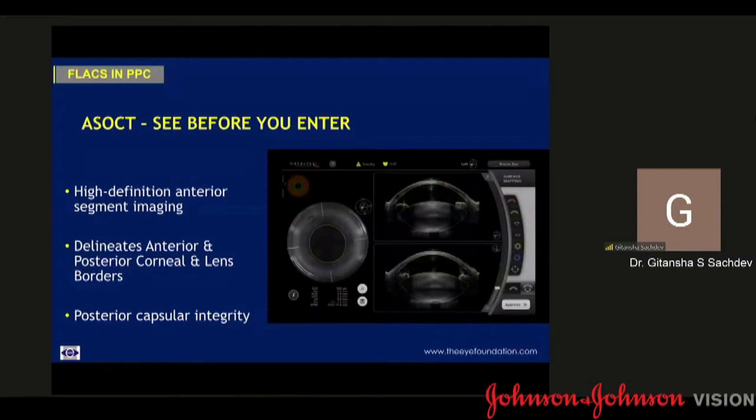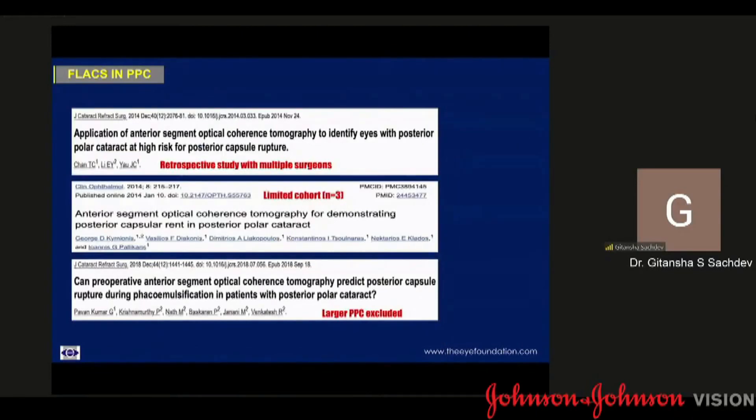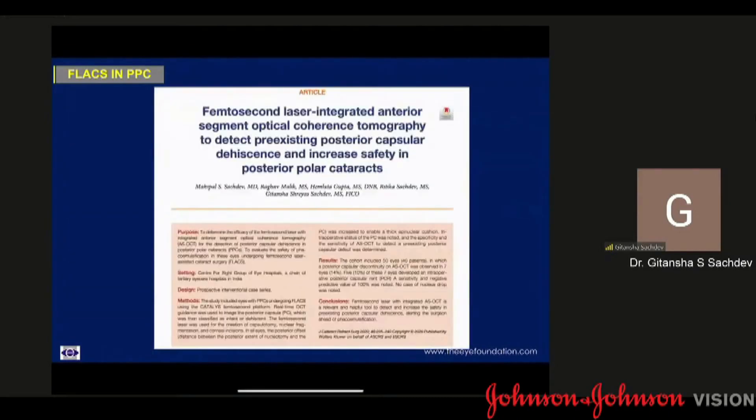One of the advantages I like best is the inbuilt AS-OCT. It is high-definition anterior segment imaging wherein you can get imaging of the posterior capsule before actually starting the surgery. This can be done at any stage — preoperatively, within the built-in femtosecond laser AS-OCT, or even intraoperatively. A handful of studies have shown the use of preoperative AS-OCT in eyes with posterior polar cataracts and conventional phacoemulsification, but with certain limitations — retrospective study with multiple surgeons, a limited cohort, or PPCs larger than 4 mm were excluded. To overcome these limitations, we did a prospective single-surgeon study wherein a femtosecond laser platform was used for posterior polar cataracts of all dimensions, with or without associated nuclear sclerosis.